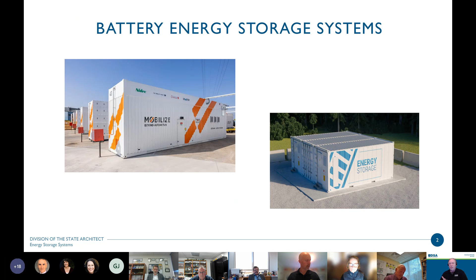So as our introduction, this comes out of section 1207 of the fire code. Battery storage systems certainly aren't new, but with the Energy Commission now directing that these be installed, we're going to see more and more of them on our campuses and within your communities. Generally, the battery storage criteria is broken out into indoor installations, which can be either in mixed-use buildings or in dedicated use buildings, and of course outdoor installations, predominantly using pre-engineered or pre-packaged units. These generally consist of uninhabited outdoor storage units placed on the campuses.